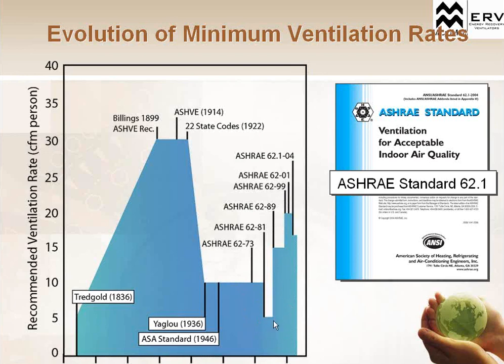Now, if any of you remember in history, this time during the early 1980s and the mid-80s is when we started seeing lawsuits and claims for sick building syndrome. This is kind of where that term came out of, because we were reducing the ventilation standards inside those spaces. People are actually getting sick. We weren't properly controlling humidity in the space with outside air. We weren't providing enough indoor air quality for the occupants in the building. So we were getting those sick buildings, quote unquote, mold issues and other things like that in the system.